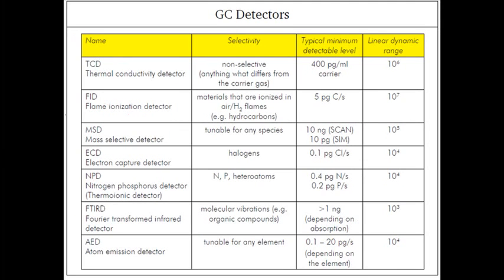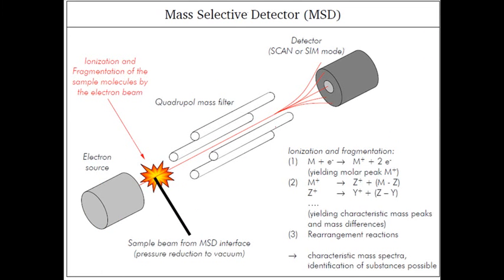We use capillary columns. The detector types we use are the thermal conductivity detector, which is non-selective, and the mass selective detector (MSD), which is tunable for every species. If you have an MSD in your laboratory it is very handy, because you can use it in different types of chromatographic separations. For HPLC you need a UV-visible detector; for GC you need a TCD, but the mass selective detector can be used for different purposes.